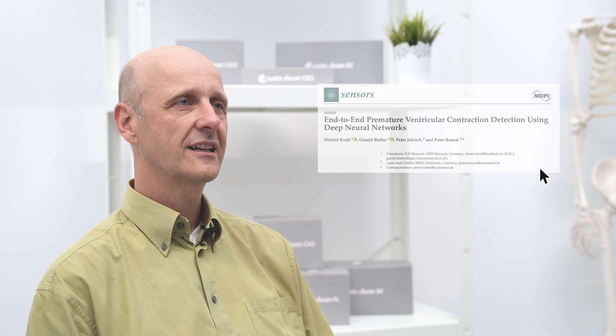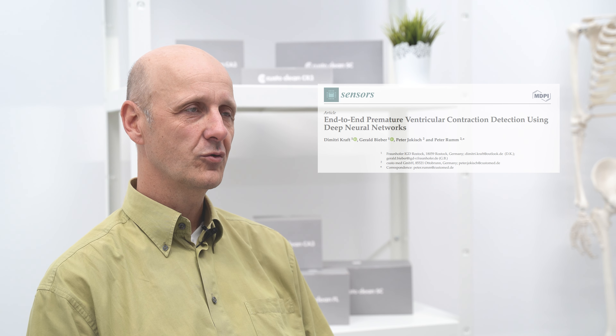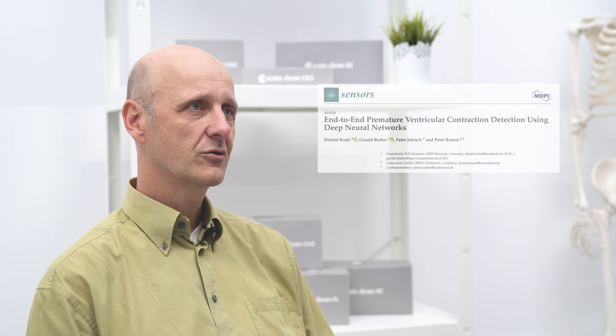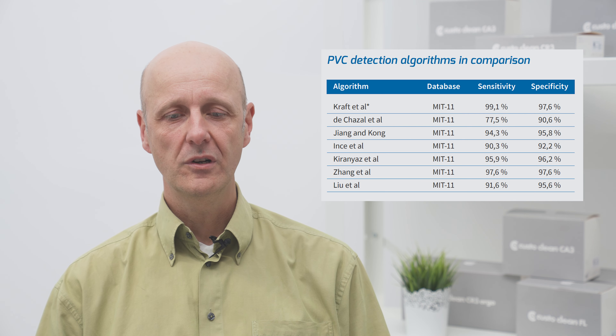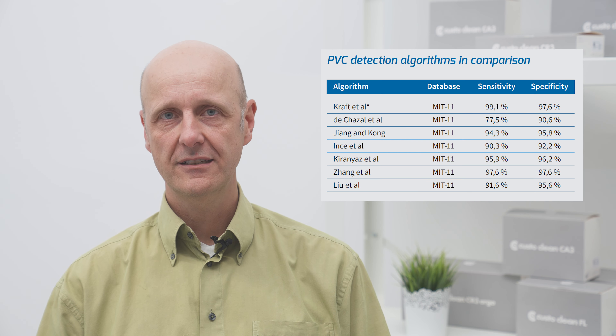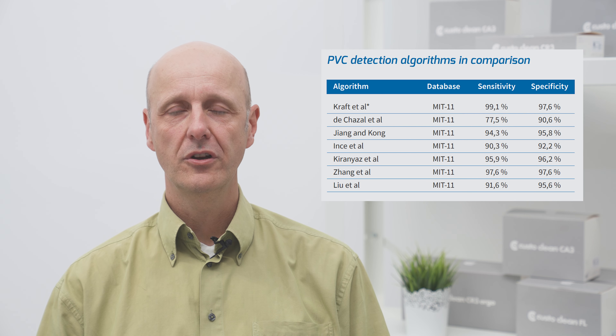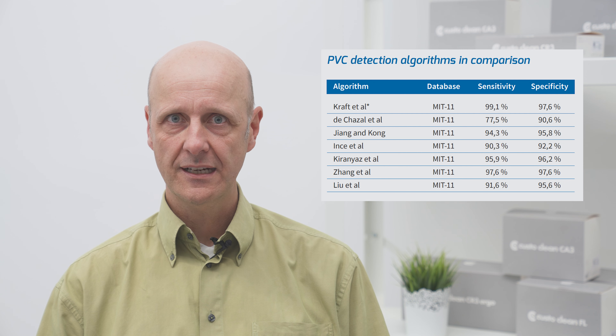We also carried out a validation study for this neural network, and in this validation study we were able to show that we can identify the normal beats with a sensitivity of 99.9% and a specificity of 99.7%.